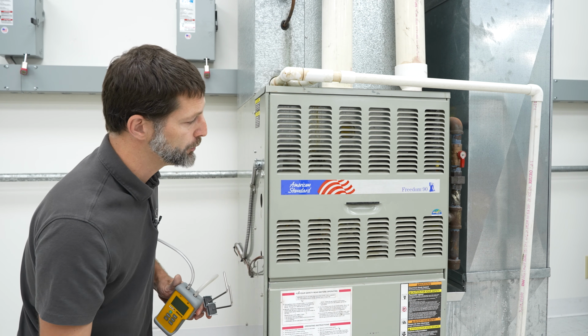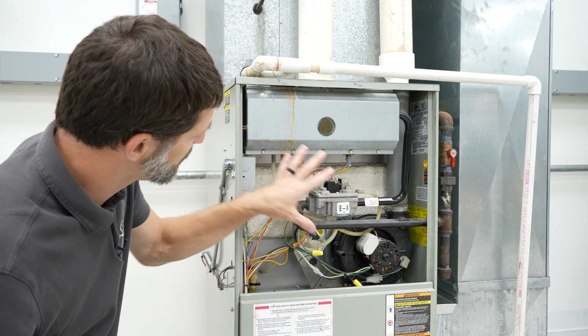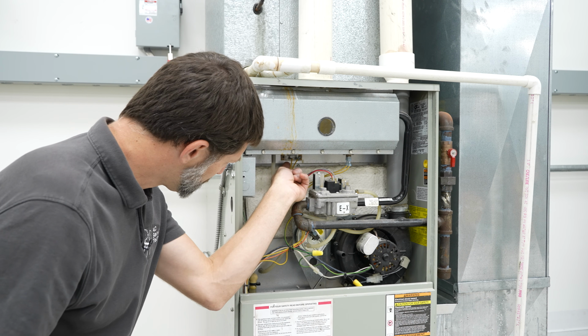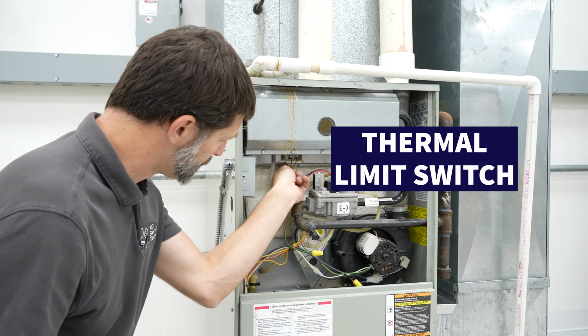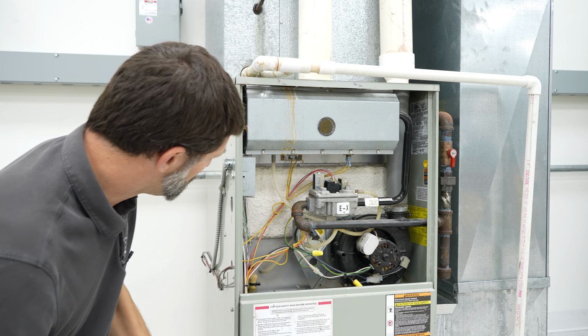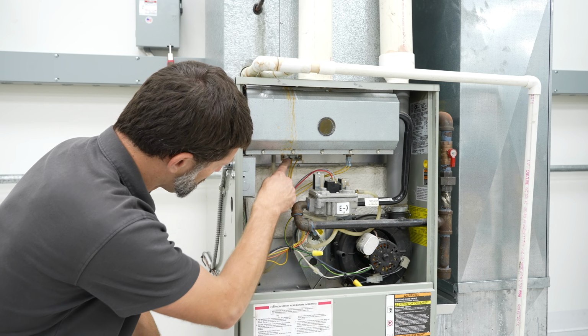So first thing we're going to do is take this cover off. Now inside of this furnace cabinet over here you're going to find the thermal limit switch. So that's up here. It could be mounted back behind the gas valve. With the power off, we're going to want to remove this.